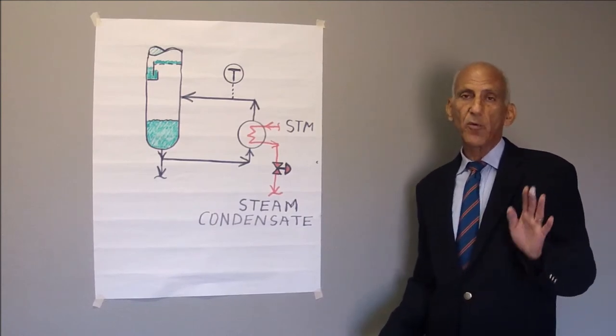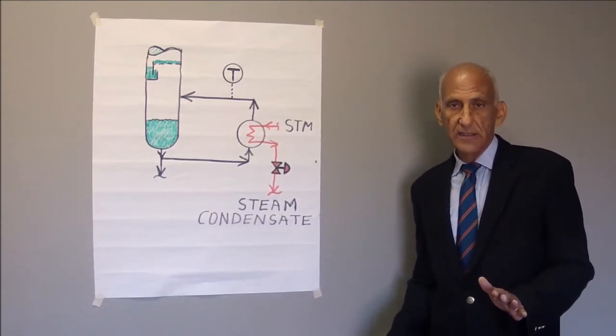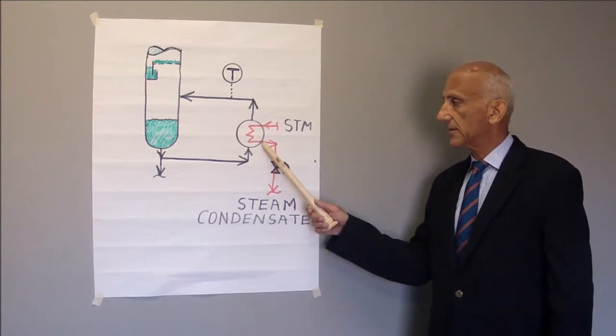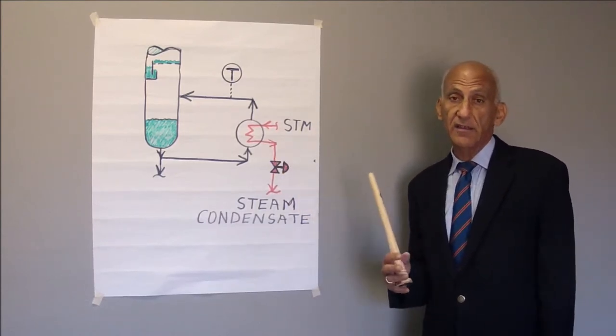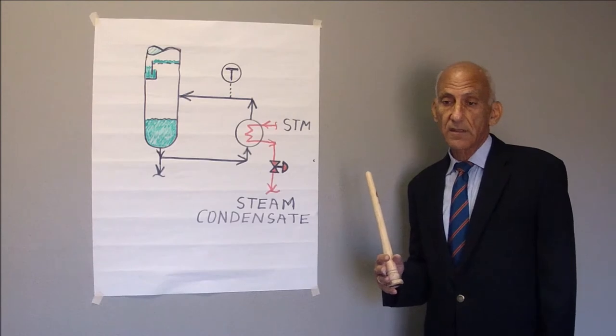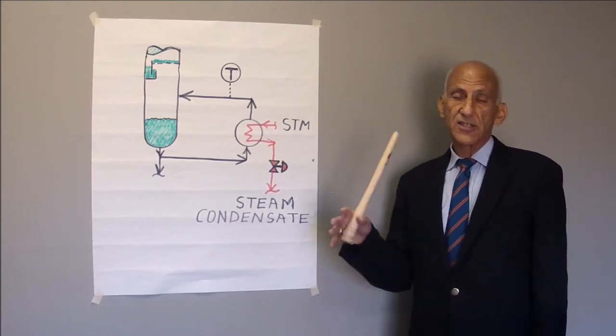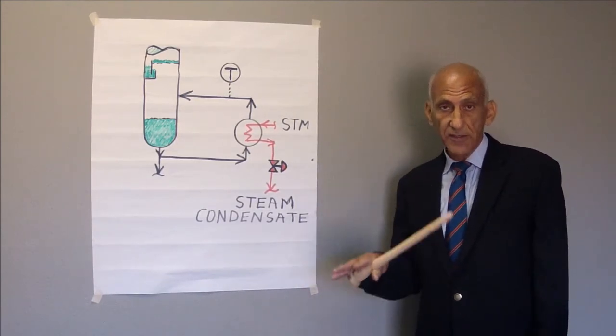And that point is when you blow the condensate seal, which simply means the liquid level in the channel head, which you cannot see, is lost, and the steam and condensate blow out together.